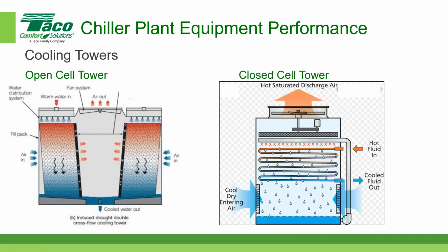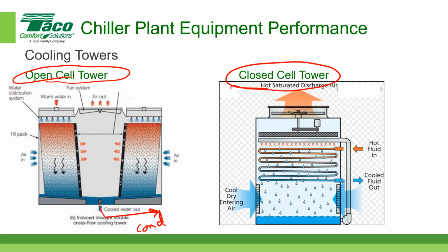So what do they look like internally? Well, again, the open cell cooling tower evaporates the water that ultimately comes in contact. This is the water that comes out into the condenser. And the water that's in the closed cell tower does not come in contact with the evaporating water. And that goes through a set of tubes and fins, and that's the heat exchange. That's this guy here, the heat exchanger. And then that water goes out to the condenser. So it does not mix or come in contact, is a better term, with the evaporating water. So that's the difference between an open cell and a closed cell tower.